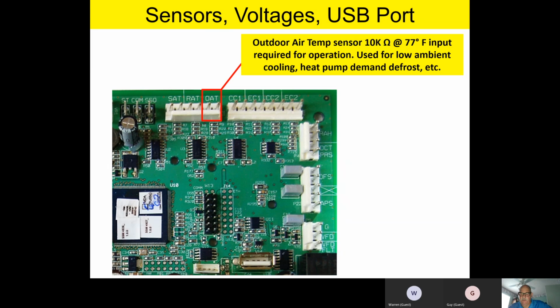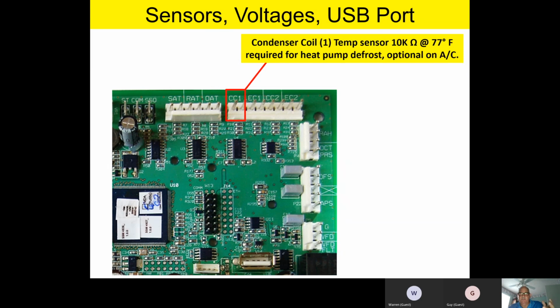Okay, next to our outdoor air temperature sensor, we're going to have another harness, and we're going to have condenser coil number 1. It's a sensor input looking at the condenser coil. It will be required for heat pump defrost operation, and it's optional on straight air conditioning units. Right next to it is the evaporator coil temperature sensor, and it is required for operation.